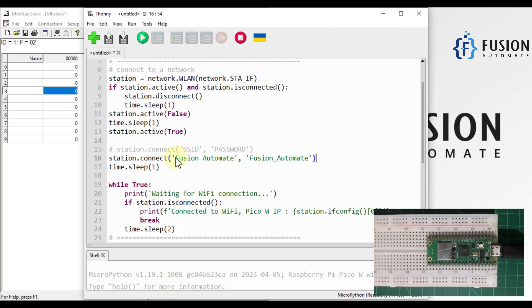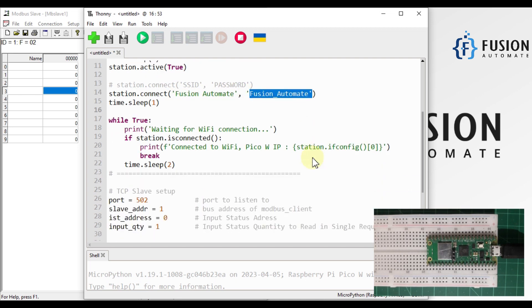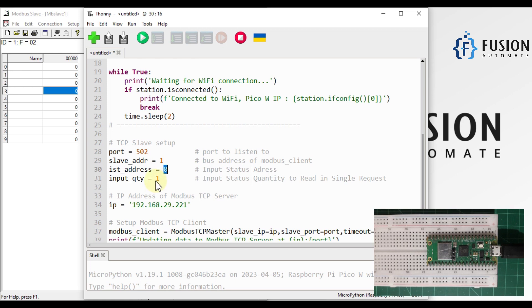Here you have to put your Wi-Fi SSID and your Wi-Fi password. The Modbus TCP port 502 is fine, and the slave address is 1 — as you can see here, device ID is 1. The input status we want to read is 0, and the quantity we want to read is 1.